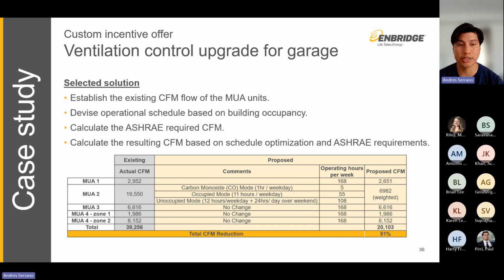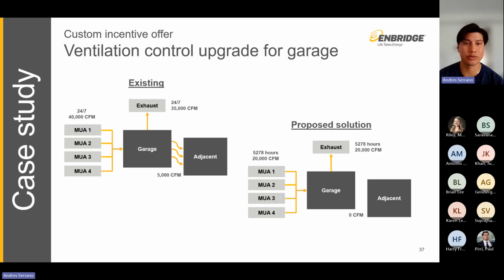in output. So we've gone from 39,000 to 20,000, and we've estimated that to have a total CFM reduction of 51%. And because we are reducing the amount of fresh air that is being pumped into the garage space, we are reducing the amount of fresh air that is being heated, thus reducing the amount of gas that is wasted to heat that air. So this more or less outlines or gives you a visualization of what is happening.